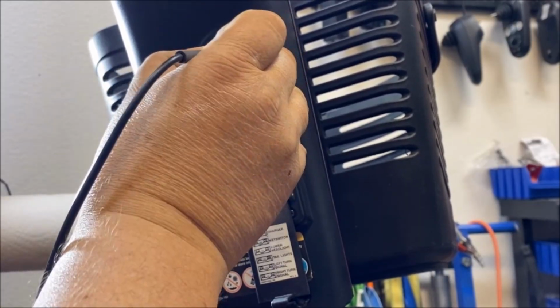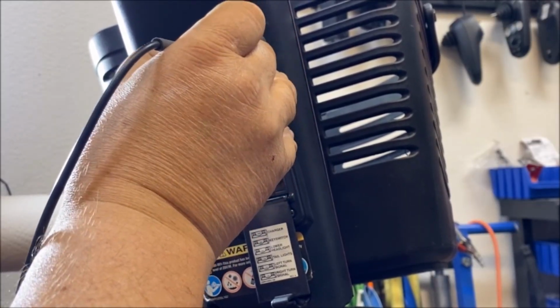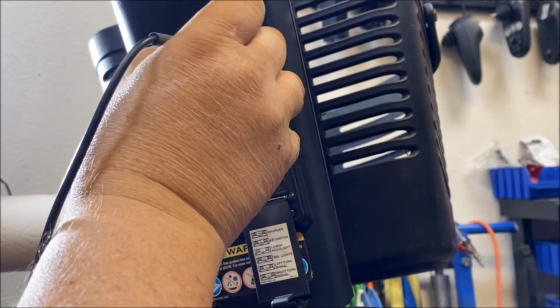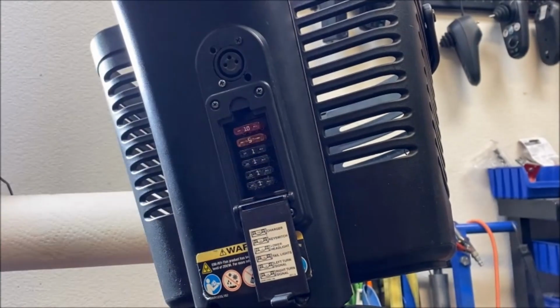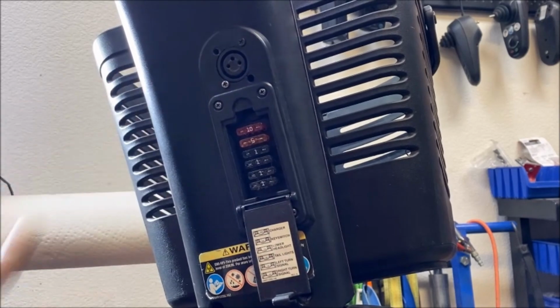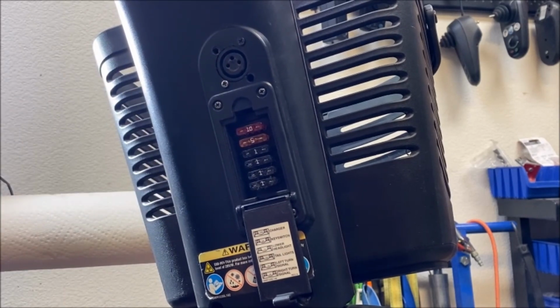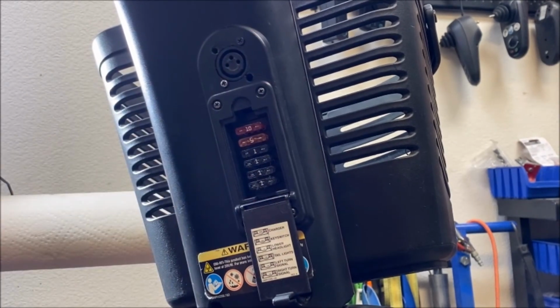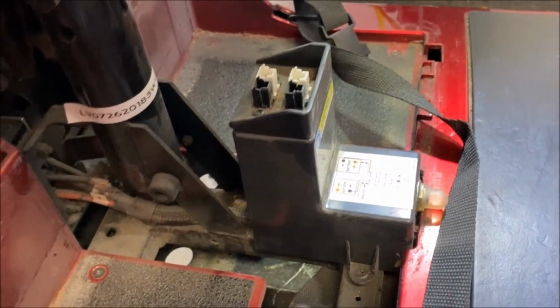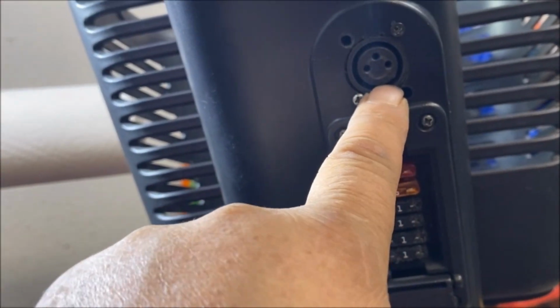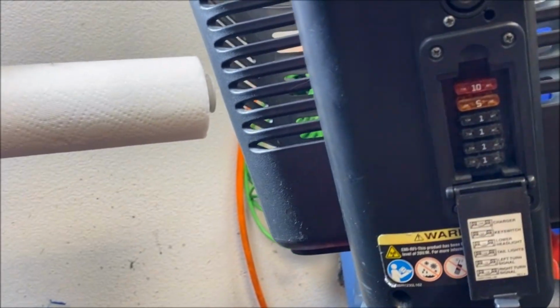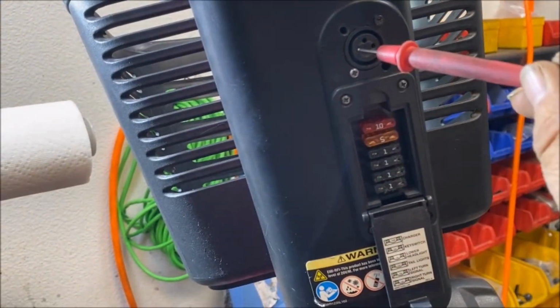So we're getting nothing at the charge port, either one. You should have continuity between there and there, because that's how you would read if your batteries were plugged in. If your batteries are plugged into the tower, you should get a reading up here of 24 to 26 volts from the battery.